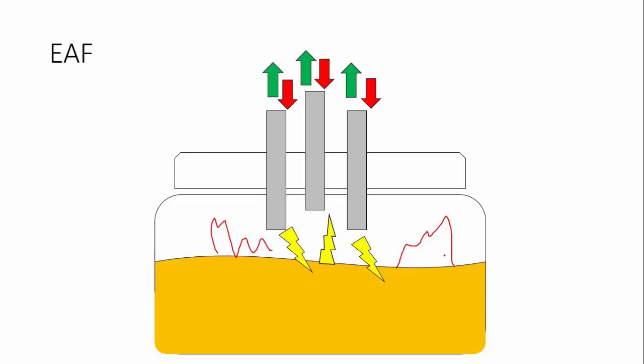Now, as you can imagine, the scrap material inside the furnace is not at all organized. It's very disorganized and very random. Therefore, the electric arc that is produced in the furnace is very erratic, and it's a completely random phenomenon. The correct word is stochastic, which means that it's very chaotic. It cannot be predicted with a lot of certainty how the arc will form or what trajectory it will follow.